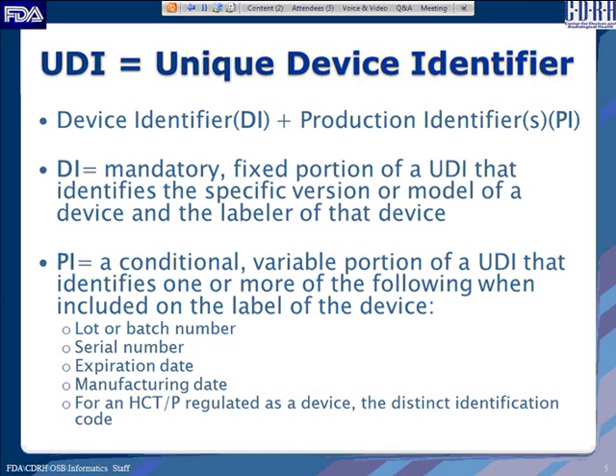So what is a UDI? A UDI stands for Unique Device Identifier. It is composed of a Device Identifier (DI) portion and a Production Identifier (PI) portion. The DI is the mandatory, fixed, static portion that identifies a specific version or model of the device and the labeler. The PI is a variable portion and may be composed of any of five items: lot or batch number, serial number, expiration date, manufacturing date, and for human cellular and tissue-based products, the distinct identification code.